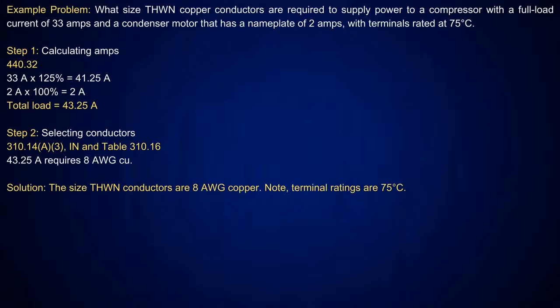But the same principle happens here. You're going to take the largest at 125%, and all other motors are added at 100%. So looking at 440.32, we take the 33 amps at 125%, which gives me 41.25 amps. Then I add the 2 amp condenser on there. That gives me 43.25 amps. Then I go to table 310.16, pick up the 75 degree C column. The next size above that's 50 amps, which is a number 8 conductor. Pretty simple.